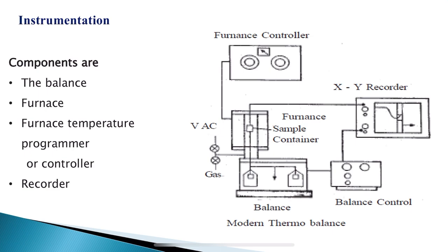So, we should be very careful in choosing the crucible for the analytical sample. A sample of around 10 mg is more than enough for the study. A thermocouple suitable for the temperature range is selected, and that is also very important. We have to choose a thermocouple whose temperature range is suitable for the analysis of the analytical sample which we have taken.